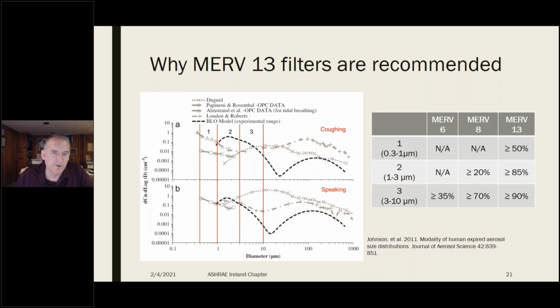For MERV 8, the filter efficiency specified in ASHRAE standard 62.1, we only have a minimum efficiency requirement of 20%, and that's in the region where most respiratory droplets are. By going to MERV 13, we move from 20 to 70%, or 20 to 85% in that range, from 70 to 90 in the largest size range, and from no requirement to 35% in the smallest size range. This is a big upgrade with a very significant effect.